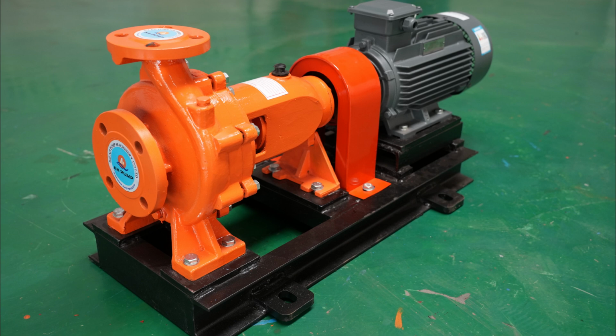So in a pump system, you can have resonance if the pump's operating frequency happens to match the natural frequency of, say, the piping. Oh, okay. And then it amplifies the vibrations, leading to more noise, potential damage. It's like they're feeding off each other's energy. Okay. So how do you deal with a pump that's got resonance? Sometimes a simple speed adjustment can shift it away from that resonant frequency, but sometimes you need more involved solutions like vibration dampeners or even modifications to the piping. Gotcha. All right, so resonance, another thing for the checklist.